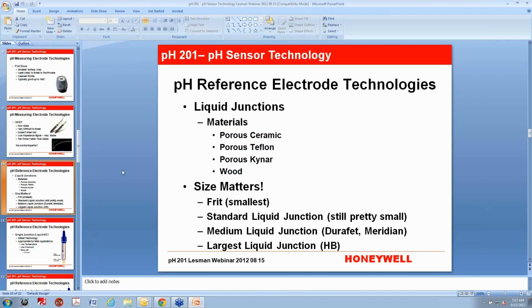Jorgi? Yes. We do have a question, and one of the questions that came up is, what's the downside of the ISFET? You may be getting into it here, but I just wanted to make sure that we had that covered for one of the members. Yeah, no, that's a good and timely question. The downside to the ISFET is that it's like Superman. If you expose him to kryptonite, he just goes down. So with a FET, there are some applications where a FET will work. I've never seen it not work. It's just a matter of how long. If you put it in hydrofluoric acid, the hydrofluoric acid is going to remove the protective coating on the face of the FET, and so then it will count all the ions instead of just hydrogen ions. So it'll immediately go up to 14 and start flashing.